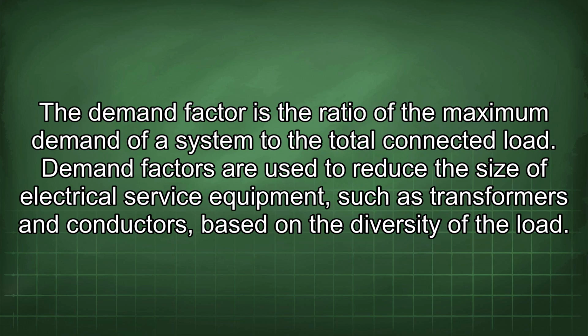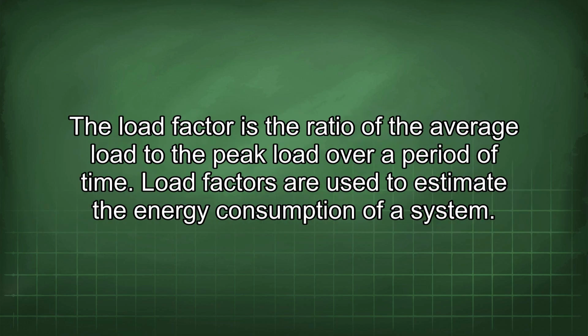The demand factor is the ratio of the maximum demand of a system to the total connected load. Demand factors are used to reduce the size of electrical service equipment, such as transformers and conductors, based on the diversity of the load. The load factor is the ratio of the average load to the peak load over a period of time. Load factors are used to estimate the energy consumption of a system.